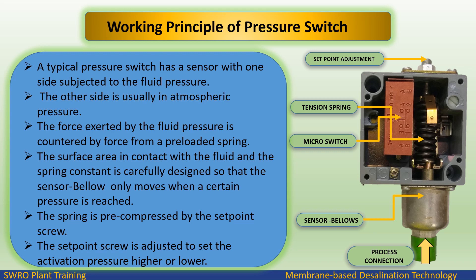A typical pressure switch has a sensor with one side subjected to the fluid pressure; the other side is usually at atmospheric pressure. The force exerted by the fluid pressure is countered by force from a preloaded spring. The surface area in contact with the fluid and the spring constant are carefully designed so that the sensor bellow only moves when a certain pressure is reached. The spring is pre-compressed by the set point screw, which is adjusted to set the activation pressure higher or lower.